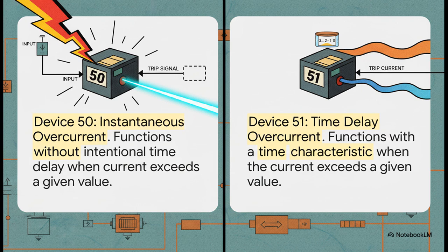Now, the difference between these two is all about timing. Device 50 is what we call the fast guard. If it sees a massive, undeniable spike in current, like a direct short circuit, it acts instantly, no delay, no questions asked. Boom. But device 51, that's our patient guard. It sees a high current, but it's programmed to wait for just a moment. Why? Well, sometimes you get temporary high currents that are perfectly normal, like when a big motor starts up. The 51 waits to make sure it's a real, sustained problem before it sounds the alarm.